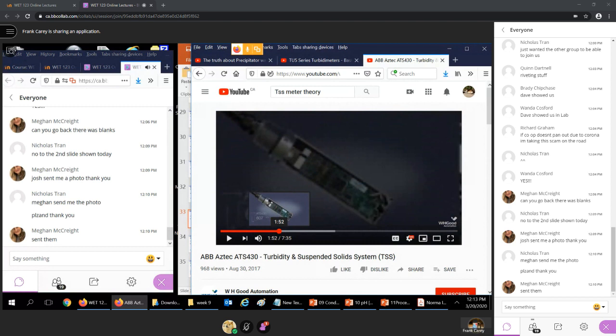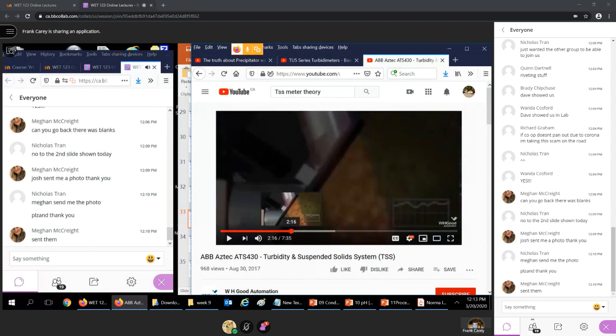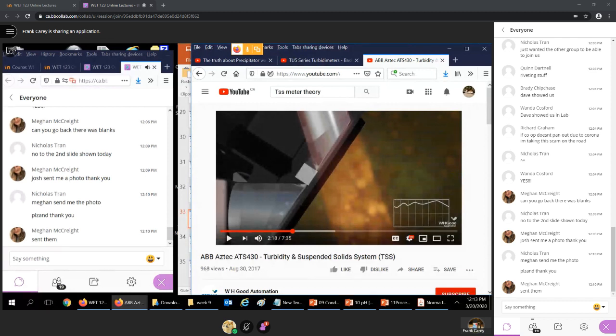Just basically a probe inside the ground. And you will see them when you go to a wastewater treatment facility, you'll see rods sticking into the effluent. And every once in a while, you'll see a little air bubble coming off, and that's just a jet of air, just to clean off the residue or whatever on the lens.